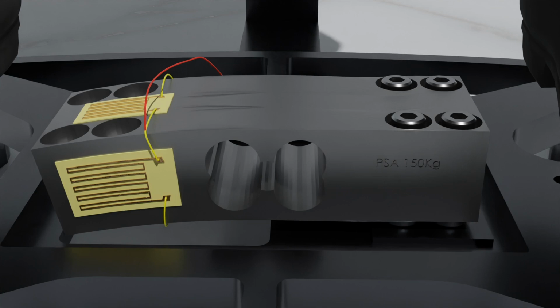These mechanisms are designed to deform or stretch in response to the force applied by the object. The extent of deformation or stretching is directly proportional to the magnitude of the applied force. Load cells commonly employ strain gauges, which are thin wires or foil strips, arranged in a specific pattern on the surface of the load cell.